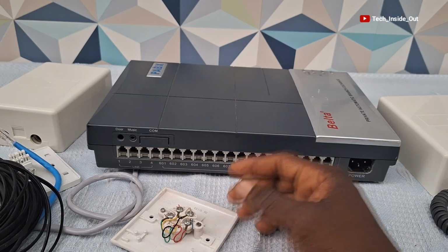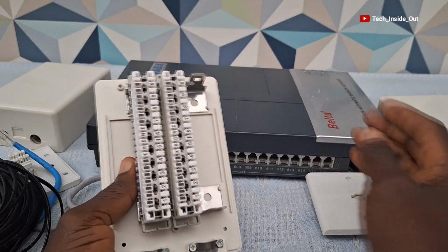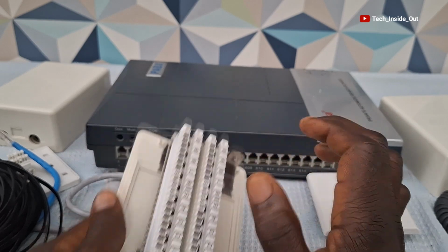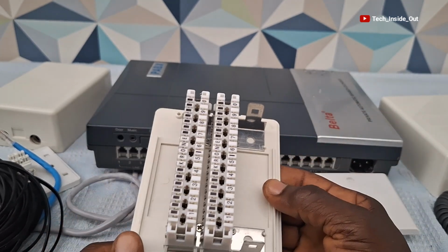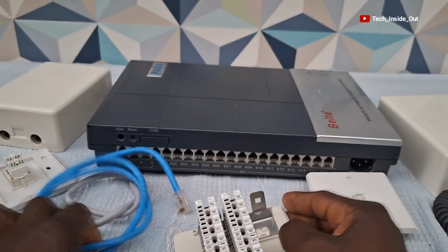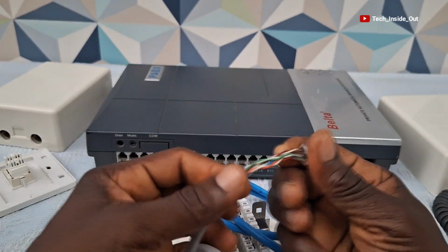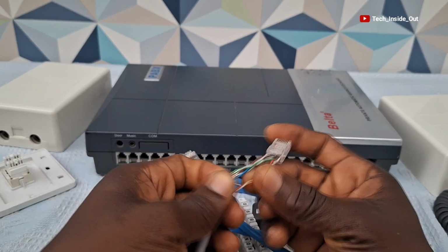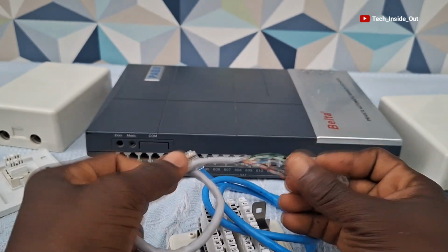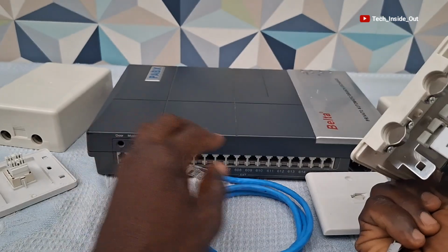Now, in the second building, you can connect all your telephone sockets onto the telephone distribution point, and then you can use a single cable. If, let's say, there are 4 extensions that you are connecting, since a Cat 6 or Cat 5 cable has about 4 pairs in it, you can use each pair for each extension and tap from the telephone distribution point into the PBX.